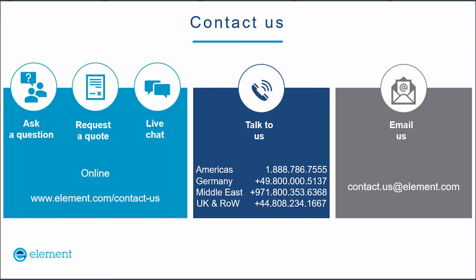Well, if you can demonstrate that the final set of results you have is applicable to your product, then you can demonstrate you have applied the harmonized standard, and therefore you can justify that you didn't go to a notified body. And that would be things like duty cycle, if you haven't changed that, if it was measured from the module, or hopping rate of Bluetooth, that sort of thing. If you haven't changed any of that, then you can say that the measurement from the Bluetooth module was identical to how it would be from your product, and you know that because it's fixed in the DSP or the firmware of the module, and you haven't changed that.